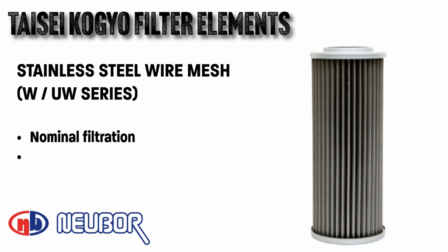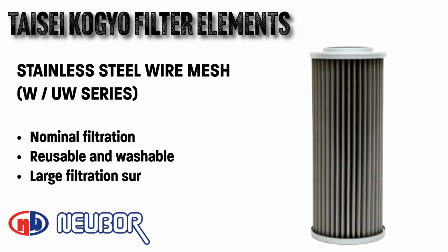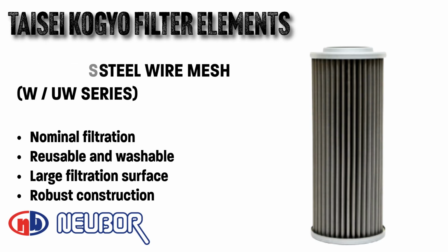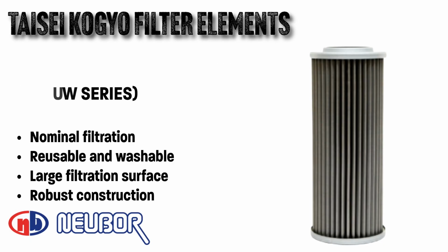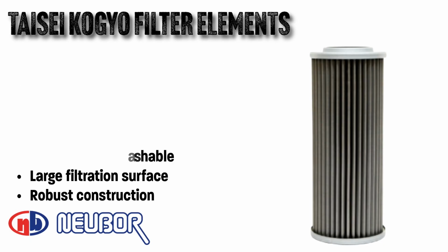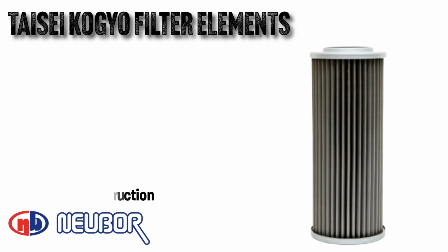Thanks to their pleated stainless steel construction, they provide a large filtration surface and high mechanical resistance. Although their initial cost is higher, they can be cleaned and reused multiple times, reducing long-term operating costs. The larger filtration area also improves dirt holding capacity and flow stability.